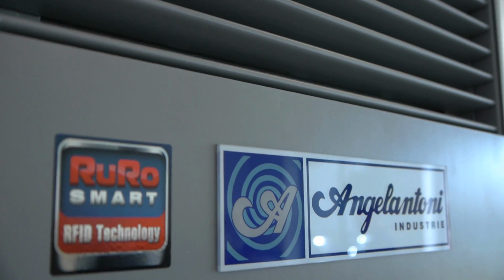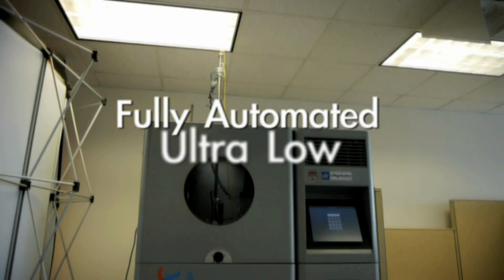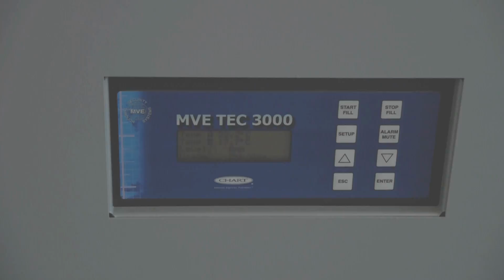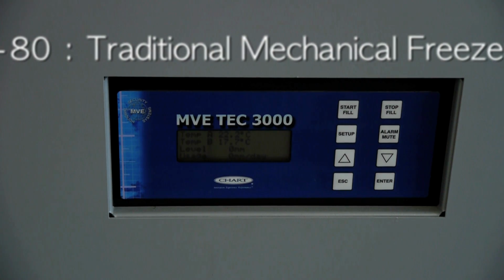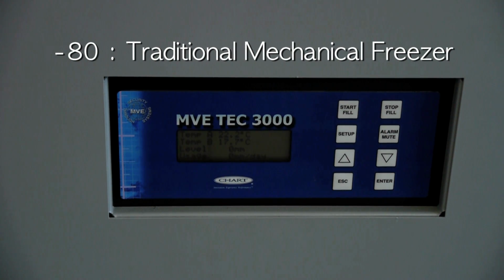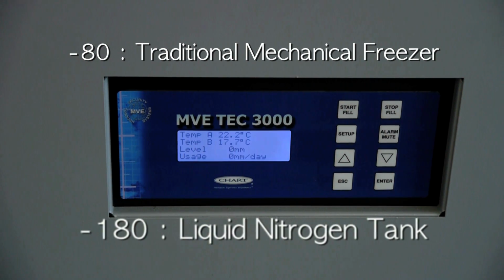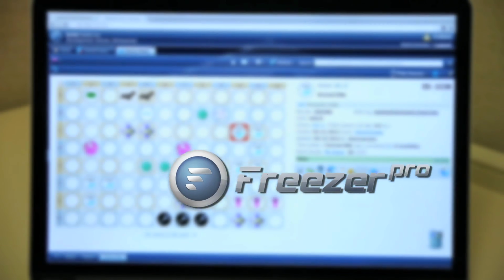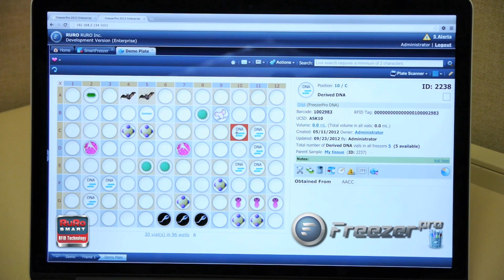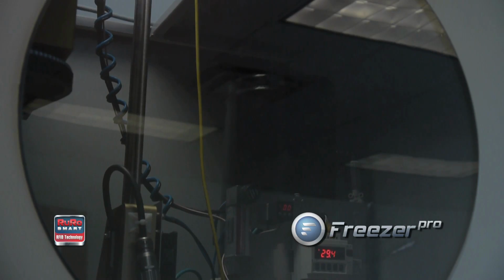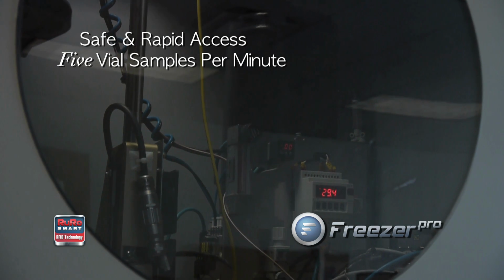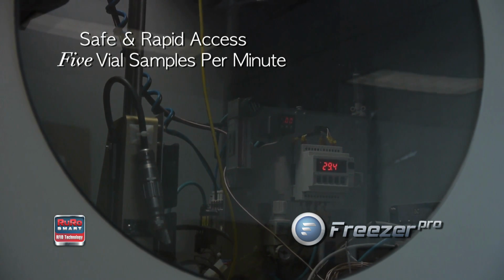Developed in partnership with Angelantoni Industrie, SmartFreezer is the only fully automated, ultra-low temperature storage system that individually stores and retrieves sample vials at temperatures of minus 80 using a traditional mechanical freezer, or at minus 180 using a liquid nitrogen tank. SmartFreezer is powered by RURO's FreezerPro sample management software and RURO's smart RFID technology.